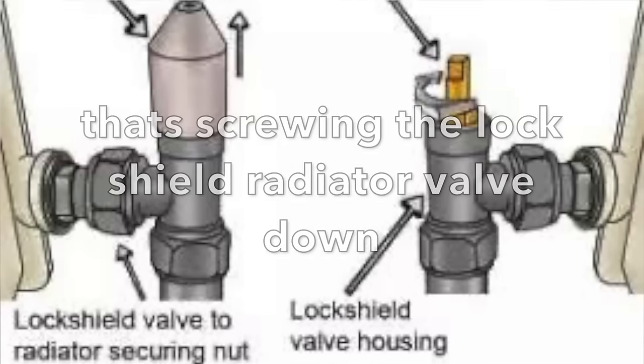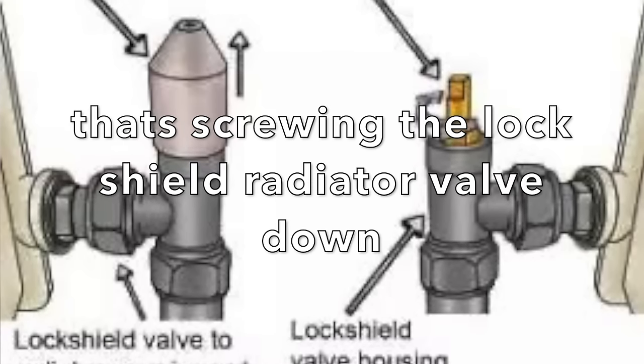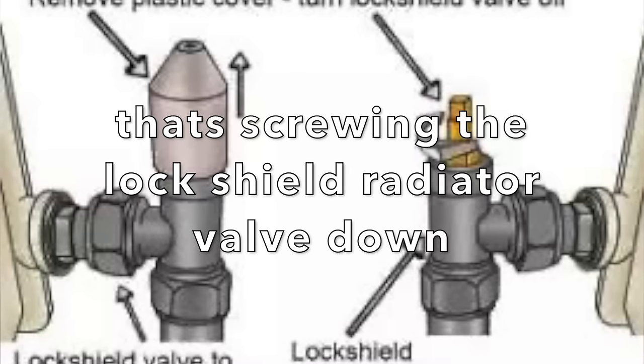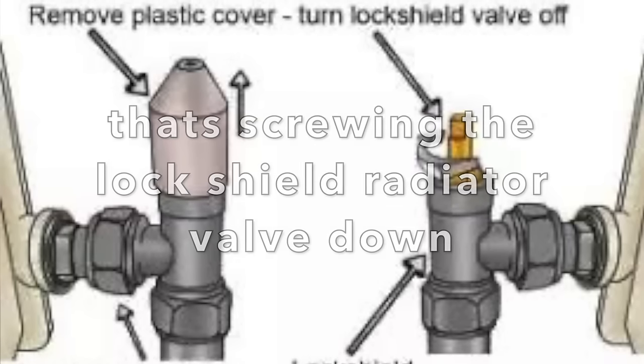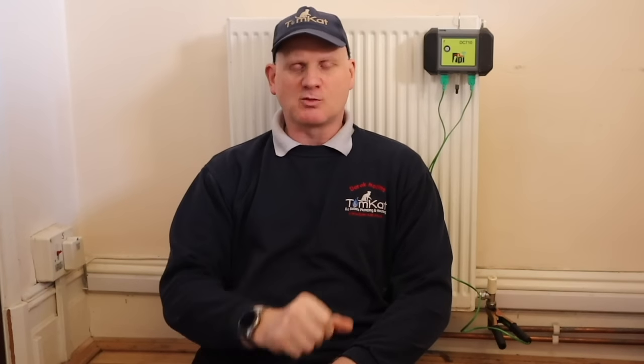Now, a lot of engineers think just going to the nearest radiator to the boiler and screwing it all the way down and turning it back a quarter of a turn, and then going to the next one and screwing it half a turn, is the way to balance a system. But the correct way of balancing a system is having a difference between the flow and return temperatures of between 10 and 12 degrees. That will give us the best system.